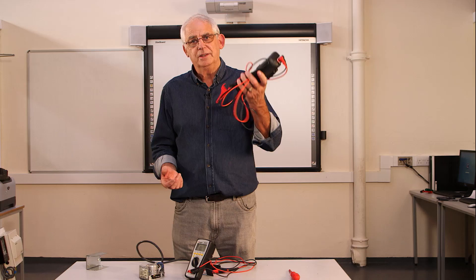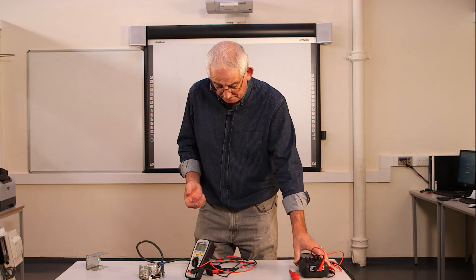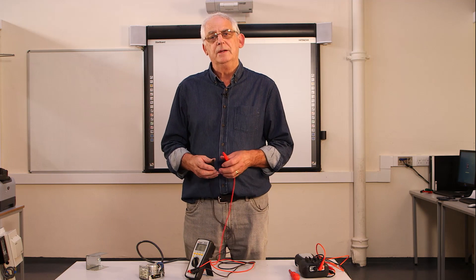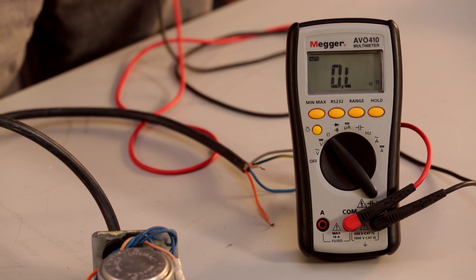The problem we've got is that the motorized valve, the synchronous motor, has got such a high resistance that this won't read low enough to check it. So we'll put that to one side and that's where we need to get ourselves a multimeter. A multimeter will read right down into k ohms which is what this needs to be.